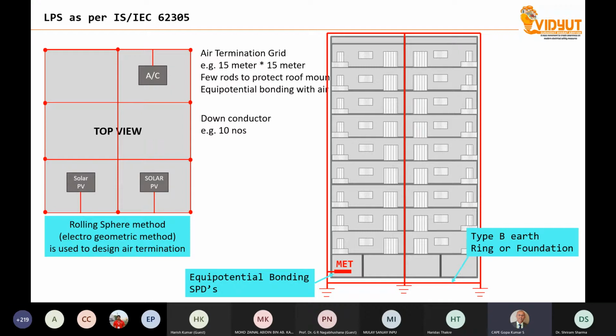So there is also some more science behind it. There is a lightning protection level and a risk assessment, and those points are there, which I am not going to explain. But in a simple building with a flat roof, you have to make a mesh at the top of the building. And if there are protruded items, such as roof-mounted electrical appliances, let us say solar PV and an air conditioner chiller unit, these protruded electrical appliances require additional protection, such as a rod. Within the protection angle, the rod protects against a direct lightning strike on these electrical appliances.